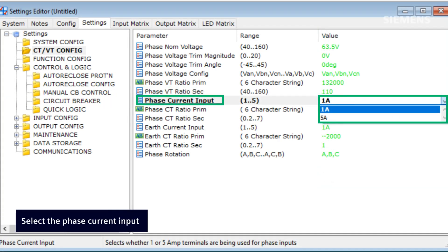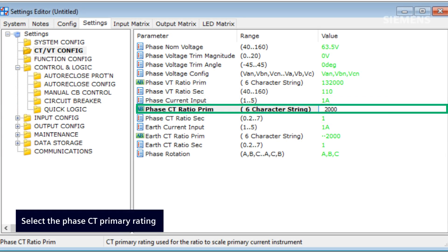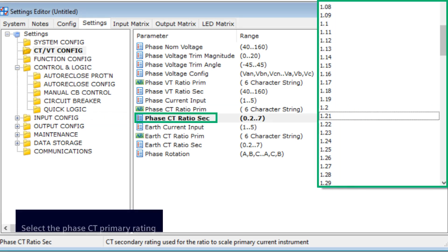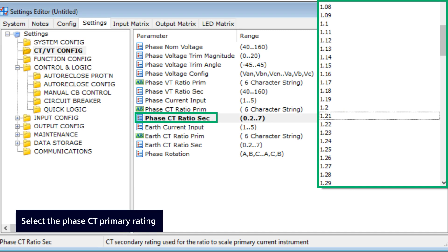The phase current input allows the user to select whether 1A or 5A terminals are used for phase CT inputs. The phase CT ratio primary setting enables the user to choose the primary rating of the phase CT, which is used to calculate the ratio for scaling the primary current measurement in the instrument. The phase CT ratio secondary setting allows the user to select the secondary rating of the phase CT, which is used to establish the ratio for scaling the primary current measurement in the instrument.